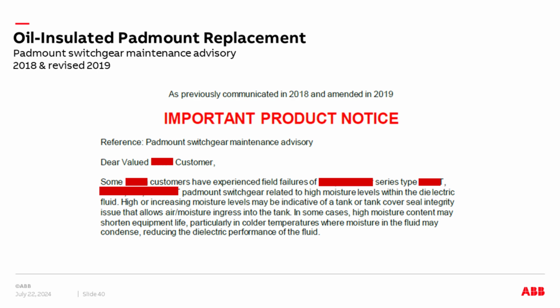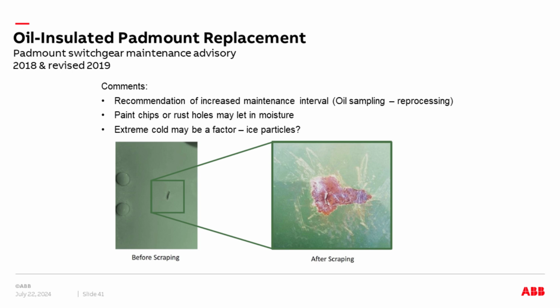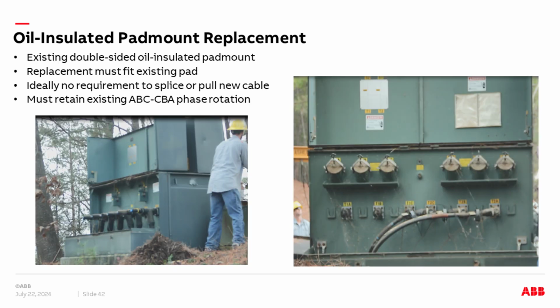There was a notice about, I blocked out the names, but it's representative of the fact that the dielectric strength of the oil insulation can go down if excessive moisture gets in. So this was an industry announcement that is on the internet, so it's publicly available. But just a point about insulation materials: they do change their characteristics if they're not in an environment where they were originally designed. And also, as part of this advisory, the metallic enclosure can be damaged or rust or end up allowing moisture into it in ways that aren't predicted. So it's something to be concerned about.